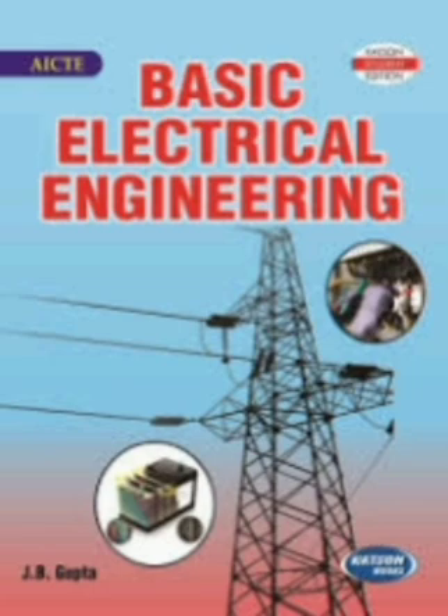Auto transformer: AB equals series winding, BC means common winding, NH means number of turns in winding AC, NL means number of turns in winding BC. Ratio of transformation, A auto equal to VH by VL equal to NH by NL. Always try to keep A auto closer to 1, that is A equal to 1. In the worst case, we try to keep A auto equal to 3:1.